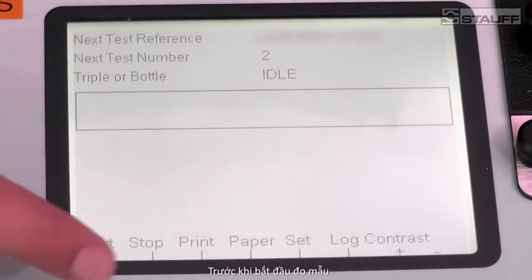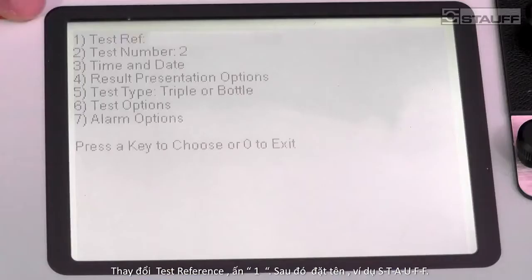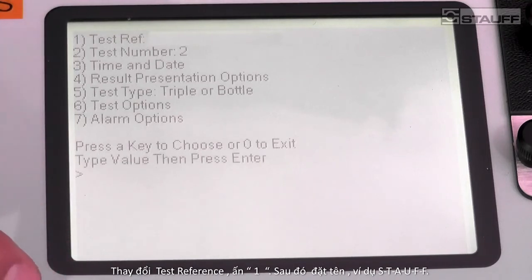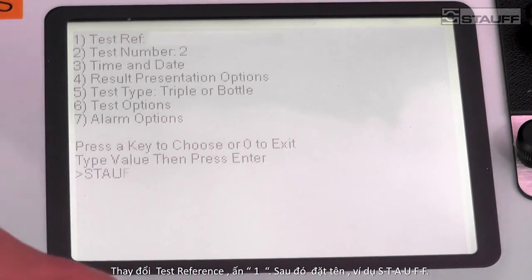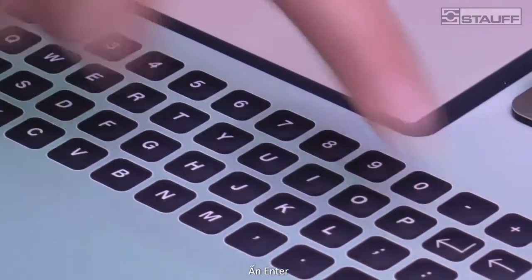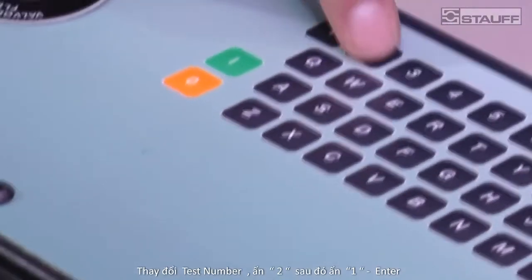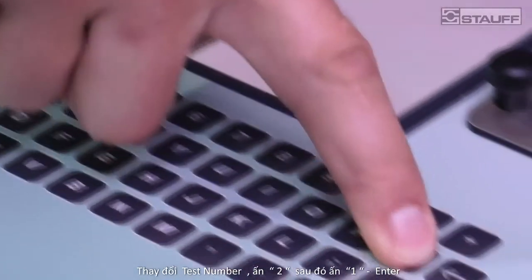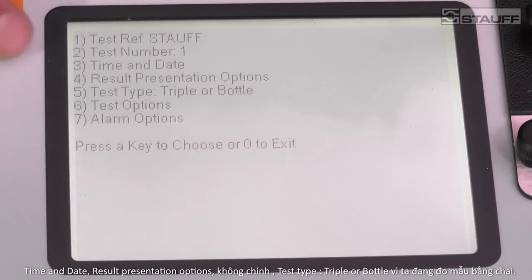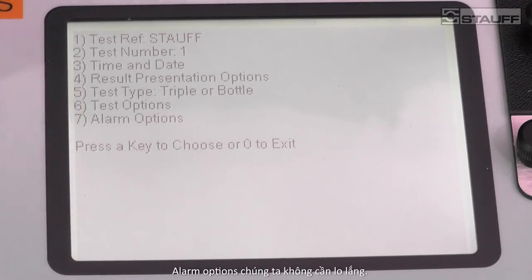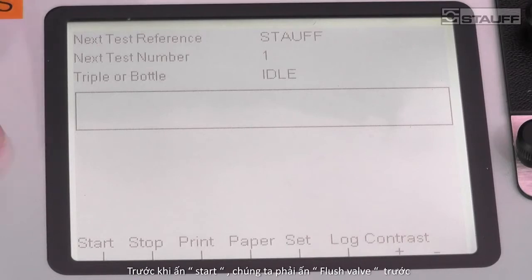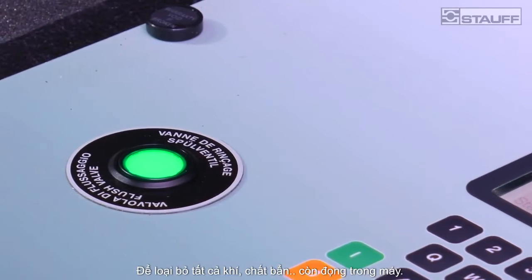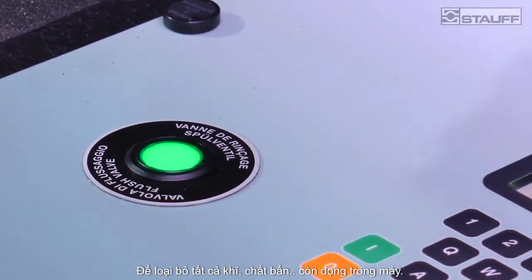Before you commence with the test, press Set and change the reference number under number one. Press one and then type in your reference — S-T-A-U-F-F — press Enter, and change the test number to number one, so press two and press one, then Enter. Time and date are okay, presentation options are okay, test type is triple or bottle because we are using the bottle. Alarm options we don't have to worry about. Press zero to go to the main menu. Before you press Start, ensure that you flush the particle counter to remove any old oil or air that's been entrapped in the system.